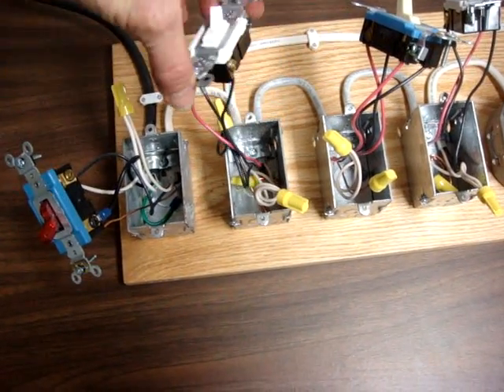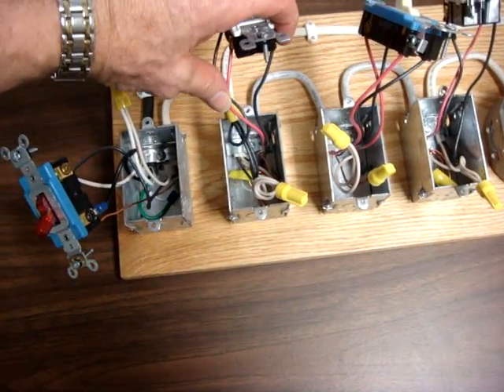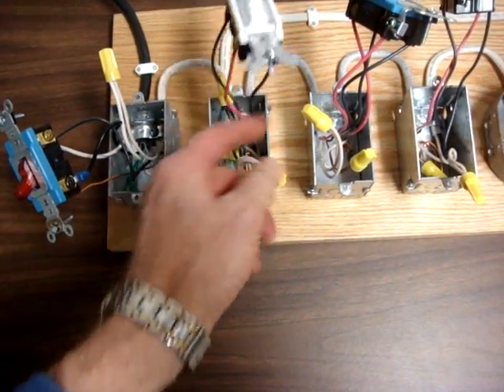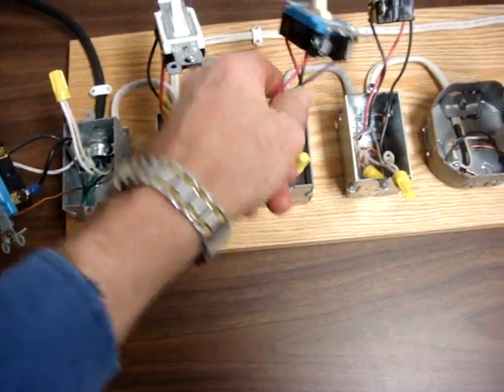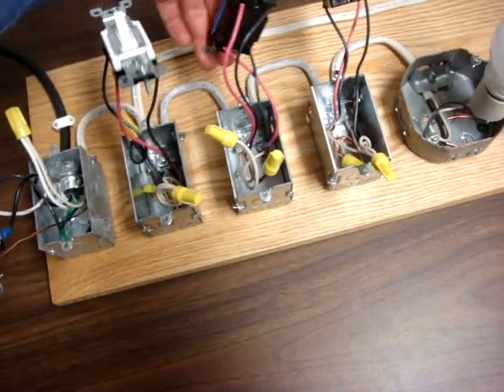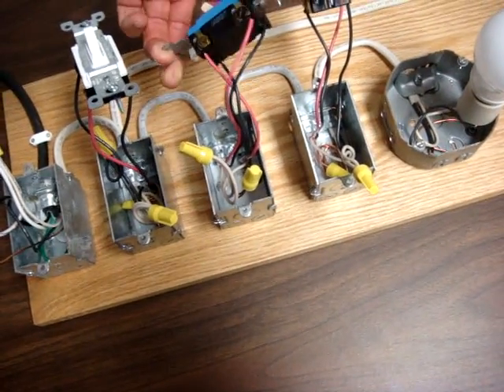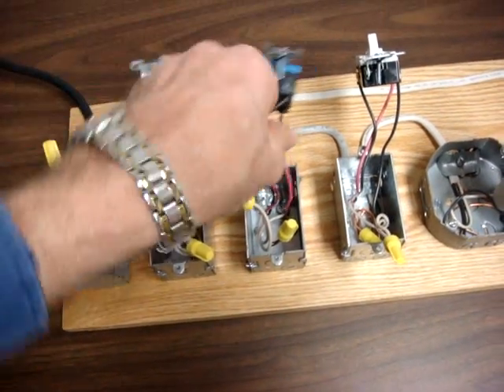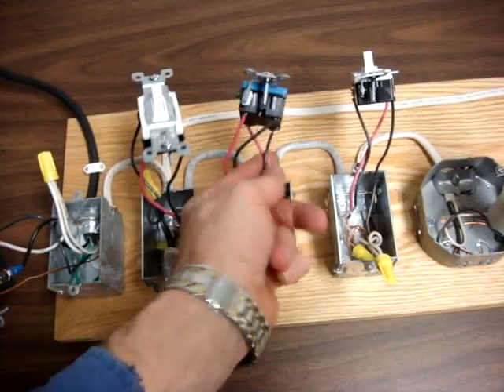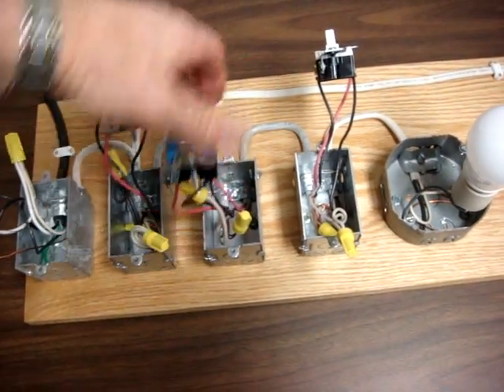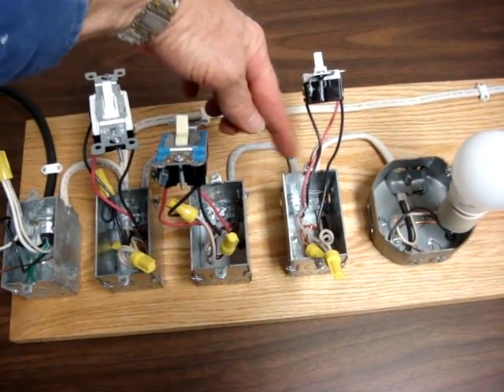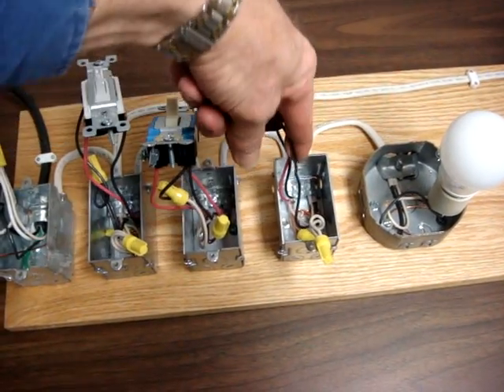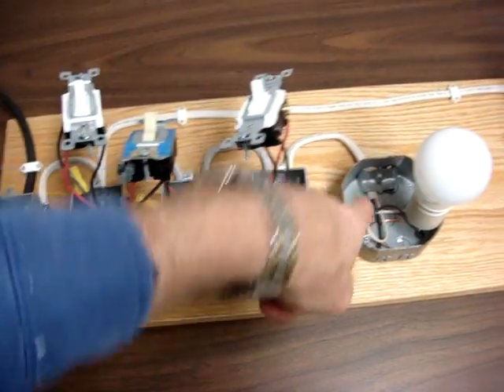The two brass terminals have what are known as traveler wires going from this switch to the next switch, in this case a four-way switch. The four-way switch has two terminals on each end. One cable comes in, goes to one end of the switch, leaves via the other end of the switch, to the three-way switch, to the travelers, and out from the common terminal to the light.